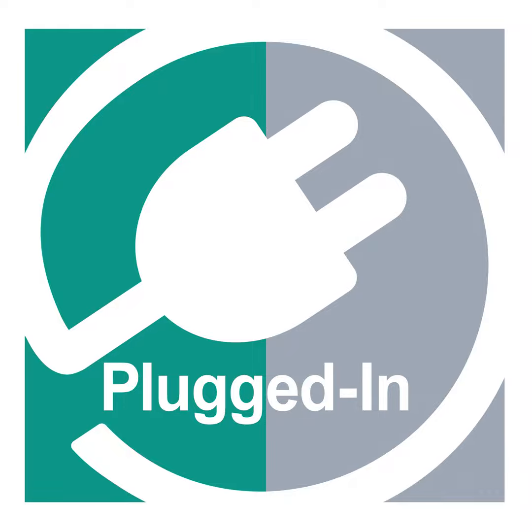Yeah, the idea of using diverse redundancy has been around for a very long time. I think what this product brings to the table is the fact that it is in one housing, and therefore it's improved with regards to simplicity. Yeah, so instead of having two separate encoders with two separate mounts and two sets of cabling, now you have one encoder that fits in the 58 millimeter housing, and it can use all of the same accessories that a normal 58 millimeter encoder can use, in terms of the mounting accessories, etc. At the same time, you have one cable instead of two that you're hooking up to your safety PLC. And it's more compact. Yes, because it's one encoder in a standard 58 millimeter housing.